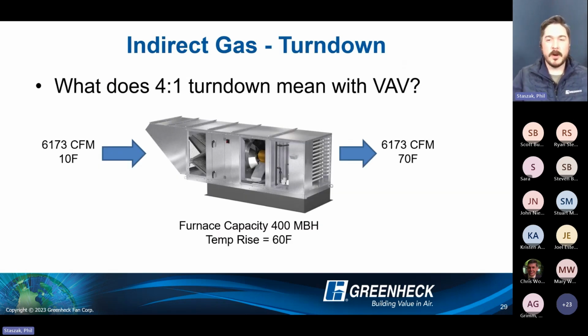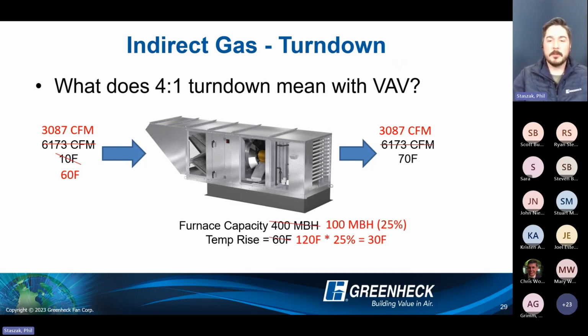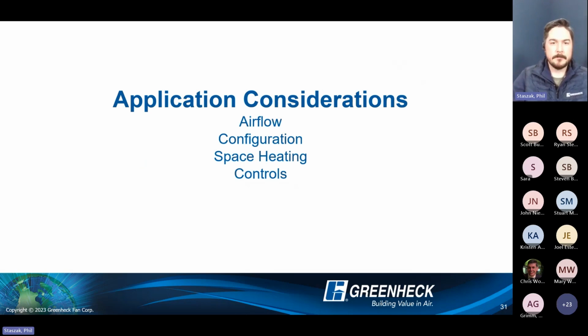Now, the other thing to consider is, what about airflow? We allow a 50% reduction in airflow in that same box. What does that look like? We reduce our system down in that same box; we're designing it for the worst case scenario. You have that same 60 degree outdoor air day and you're at minimum airflow in that box. You just doubled your available temperature rise, so now that thing's going to cycle even more. Even your design temperature rise of 60 doubles to 120 degrees. And then at minimum, at 60 degrees entering air, your minimum discharge air is 90 degrees now. So that furnace is going to cycle on and off a lot more frequently if we're looking at lower airflow in that same box as well. So just all things to consider.